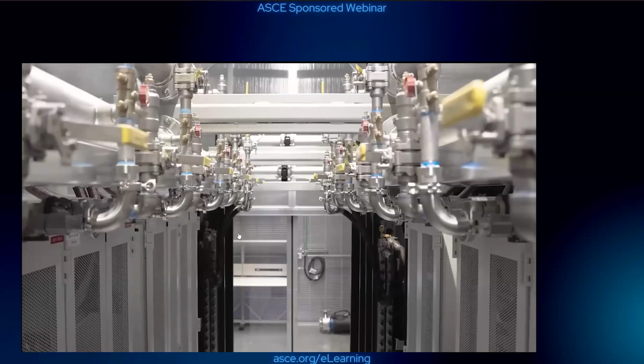This method uses pipes to circulate liquid, typically either water or a specialized coolant, to quickly and efficiently absorb heat directly from the equipment. Liquid cooling is effective because liquid conducts more than 3,000 times as much heat as air and requires less energy to do so. That efficiency allows data center operators to stack more servers into fewer racks for higher density arrangements that can meet growing processing demand while saving energy.